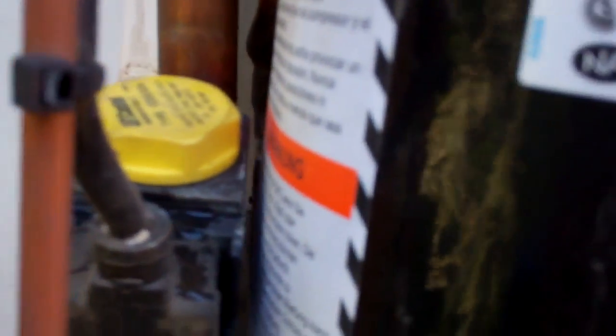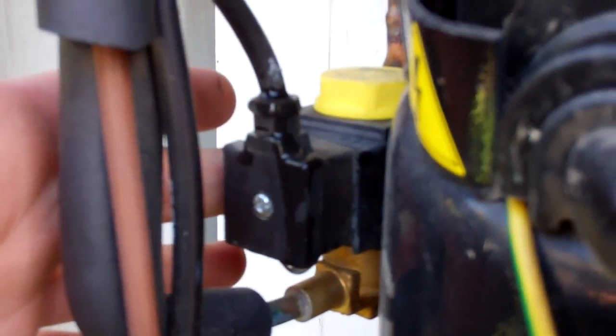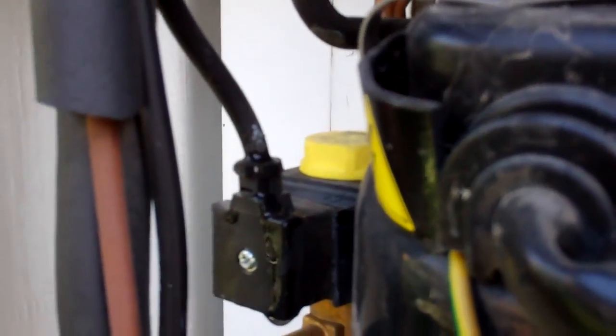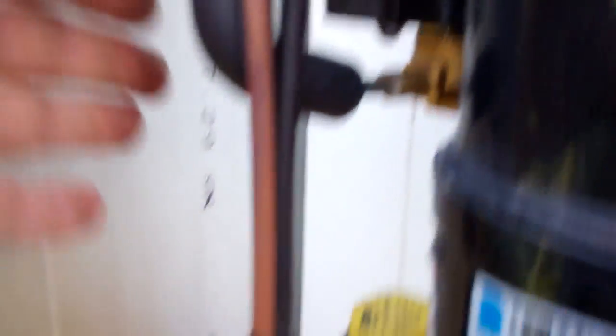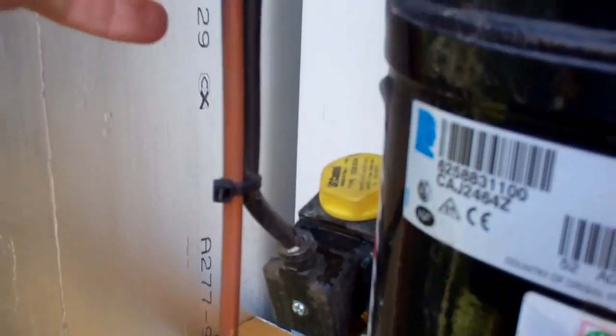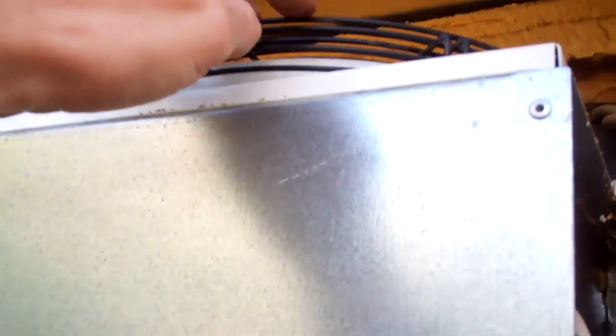So I just thought I'd try it on defrost, see what it did, hot gas defrost. One solenoid lets the gas go through the condenser. The other solenoid is a hot gas valve, so either one is open. When it goes on hot gas it shuts the condenser fan off.